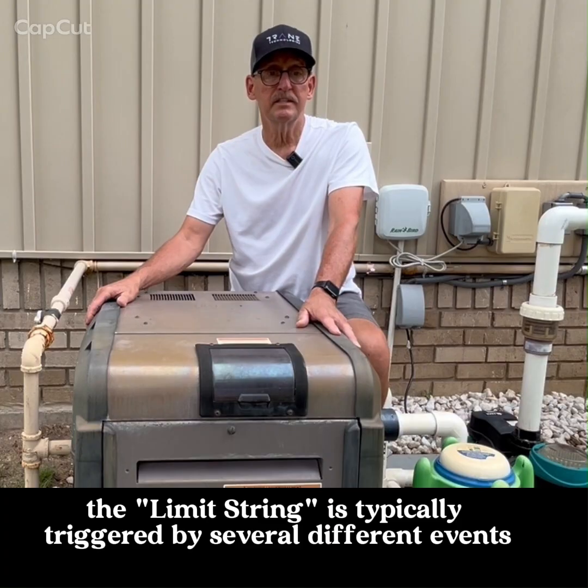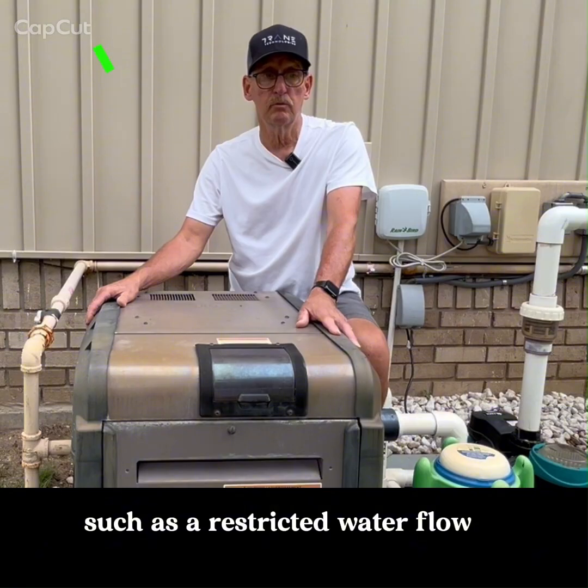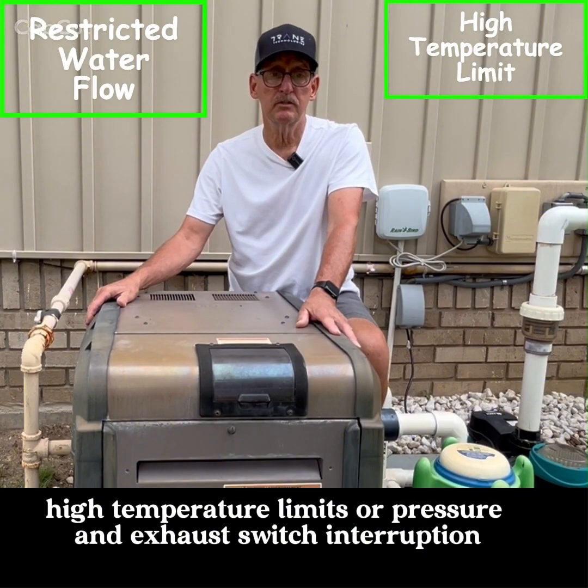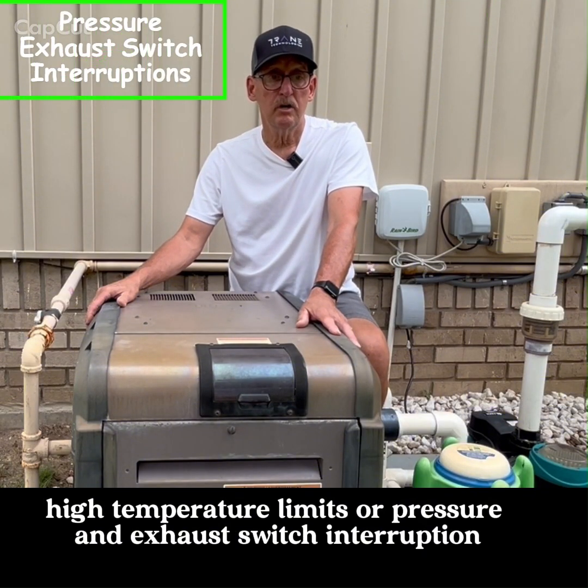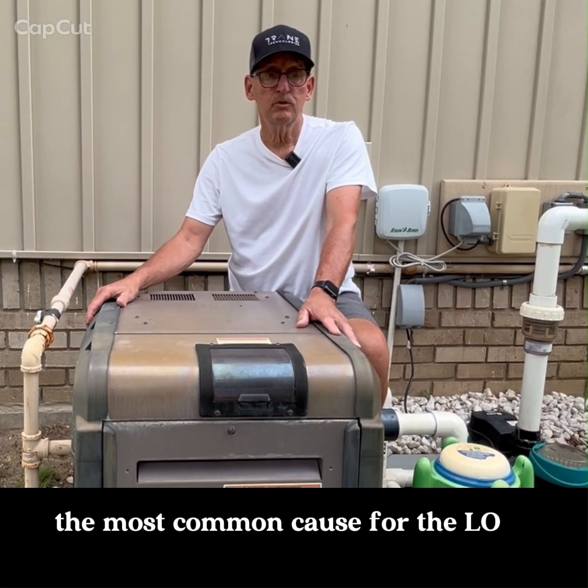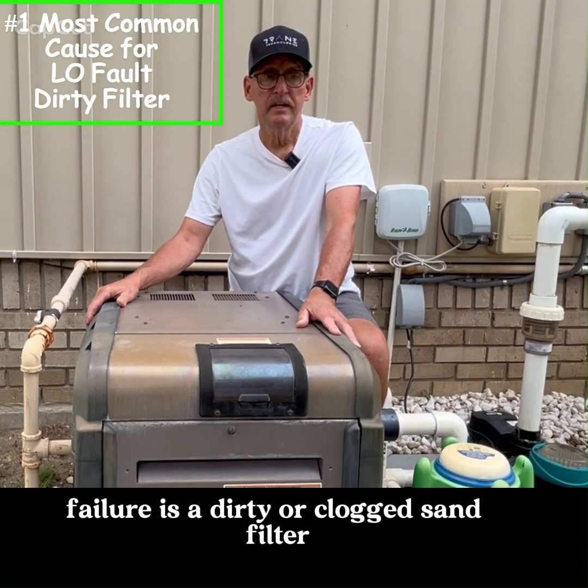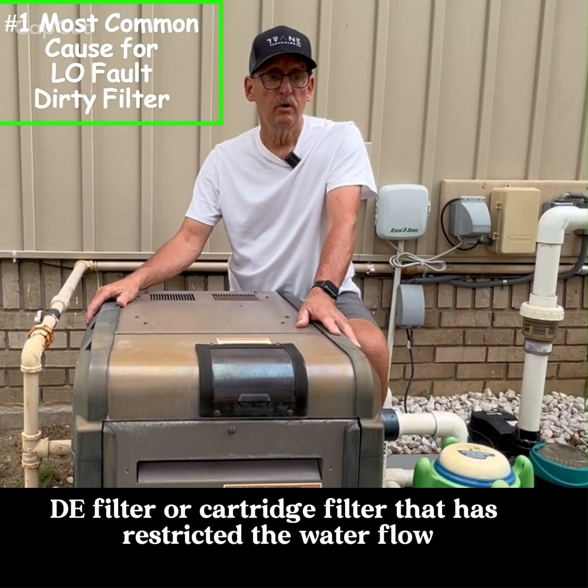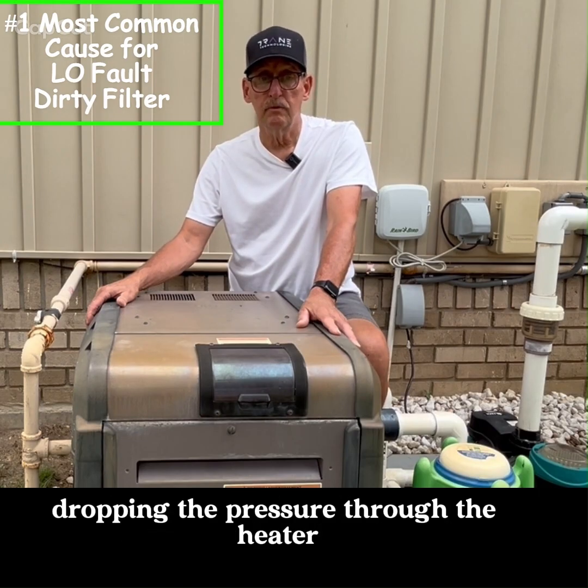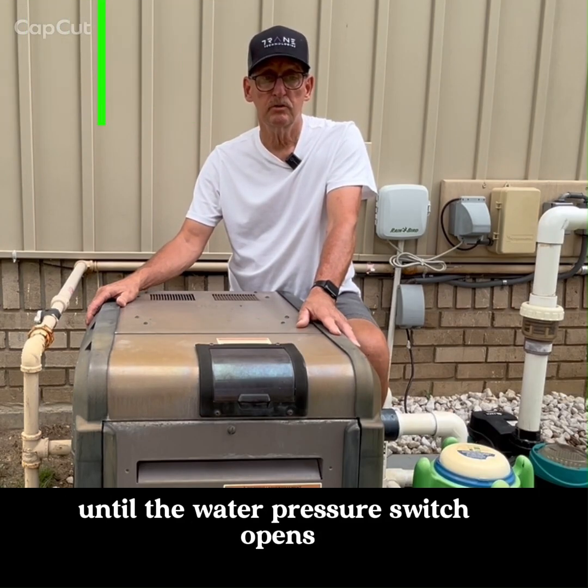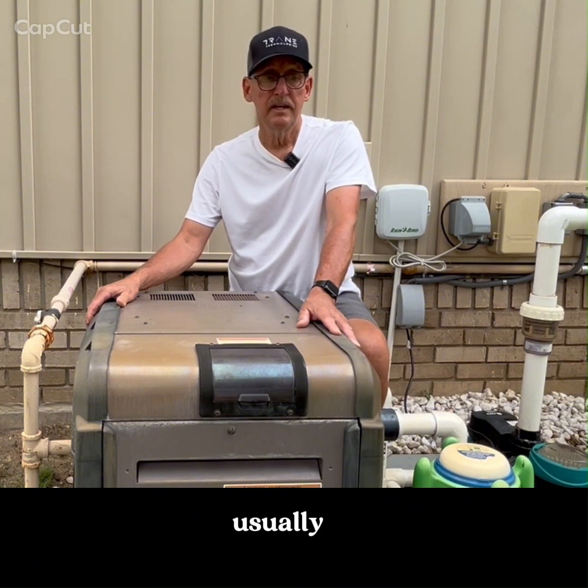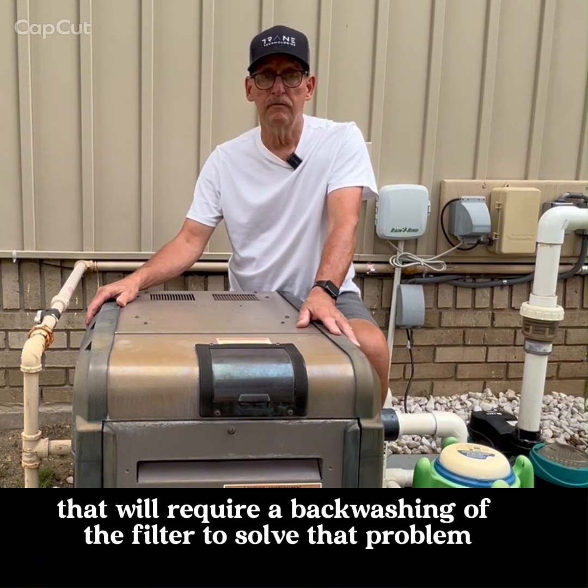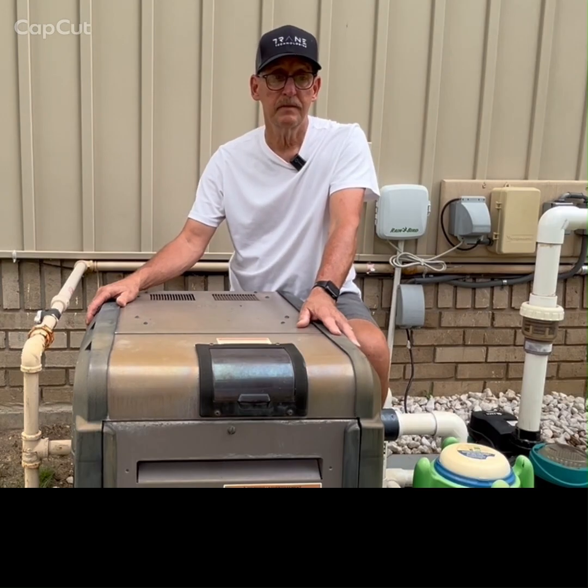The limit string is typically triggered by several different events, such as a restricted water flow, high temperature limits, or pressure and exhaust switch interruption. The most common cause for the LO failure is a dirty or clogged sand filter, DE filter, or cartridge filter that has restricted the water flow, dropping the pressure through the heater until the water pressure switch opens. Usually, that will require a backwashing of the filter to solve that problem.